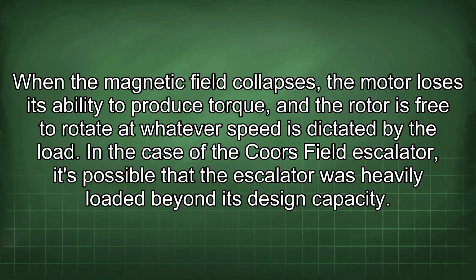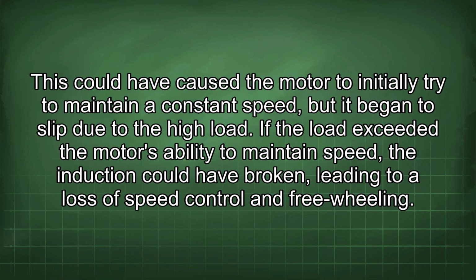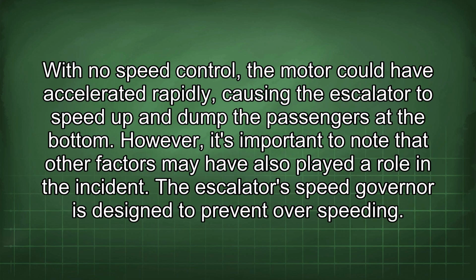In the case of the Coors Field escalator, it's possible that the escalator was heavily loaded beyond its design capacity. This could have caused the motor to initially try to maintain a constant speed, but it began to slip due to the high load. If the load exceeded the motor's ability to maintain speed, the induction could have broken, leading to a loss of speed control and freewheeling. With no speed control, the motor could have accelerated rapidly, causing the escalator to speed up and dump the passengers at the bottom. However, it's important to note that other factors may have also played a role in the incident.